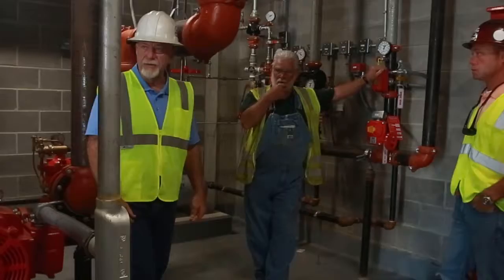Can we test those pumps separately? Like you say they're sequential, on test day we can test them. So that's what we do here. We run one pump, and then we run the second. Understand, a sequential start means that as long as the pressure's being satisfied, the other pump's not going to interact anyway. Yeah, that's why I asked. So run the other one manually. Yeah, one is the primary pump and the other one's the slave pump. So the primary pump's going to do what it can do until it can't, and then the secondary pump kicks on. So they can be tested any way you want to do it. Well, y'all want to move into the pump room so we can take a look and see what we got?